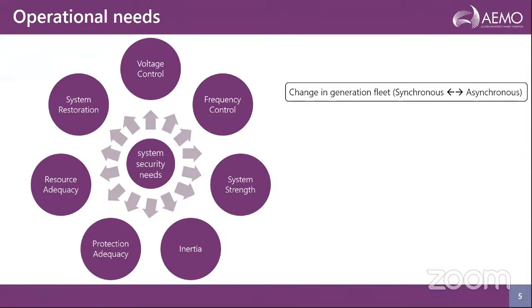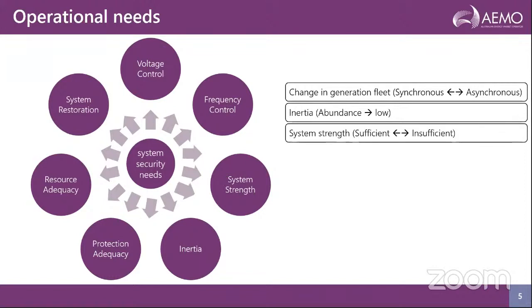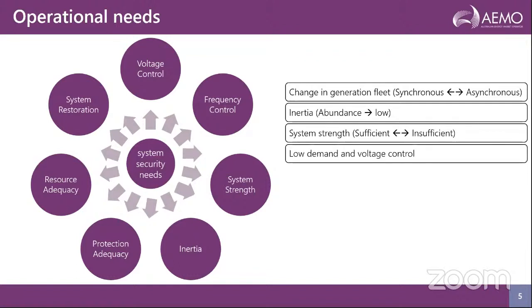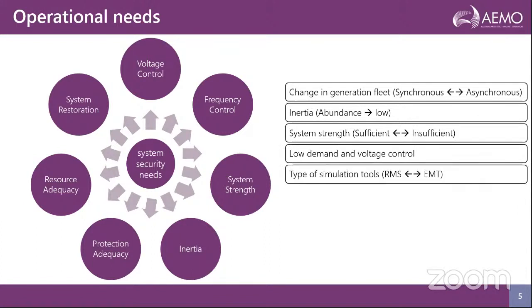We are noticing change in the generation fleet. At times the grid is dominated by synchronous generation, while there are times when the grid is dominated by asynchronous generation. Inertia of the grid would change depending on the generation online and can often be very low. There are a few challenges associated with managing system strength in low demand periods, which necessarily needs sufficient voltage control. The analysis of the system often needs to adopt an appropriate tool to assess system security. It could be an RMS tool, or it could be an EMT tool, depending on how you are operating your grid.